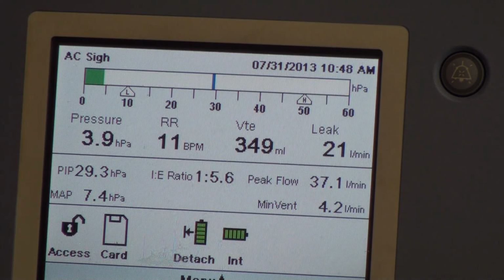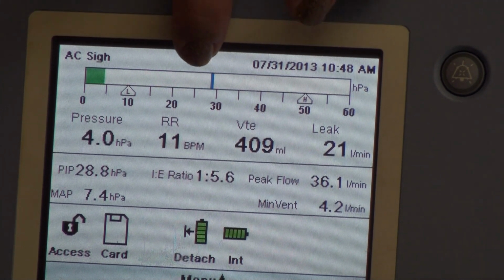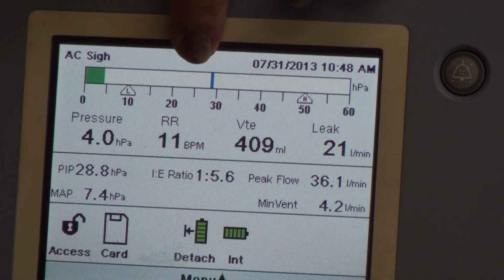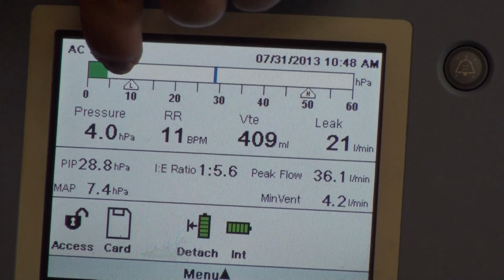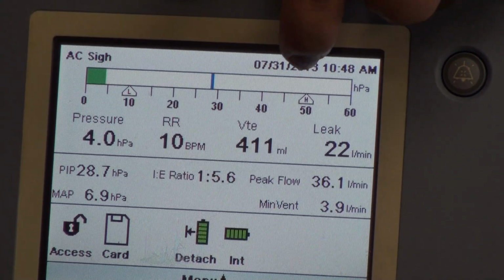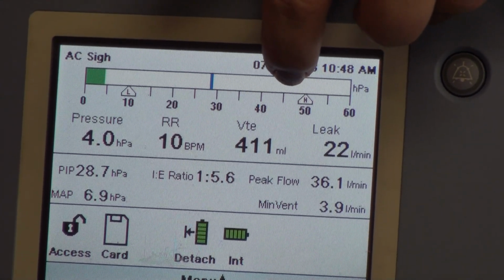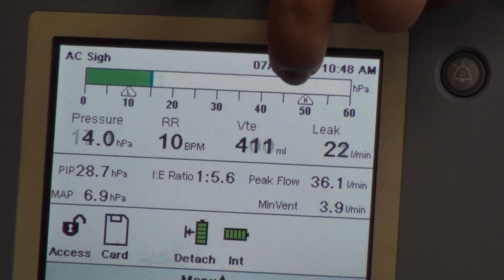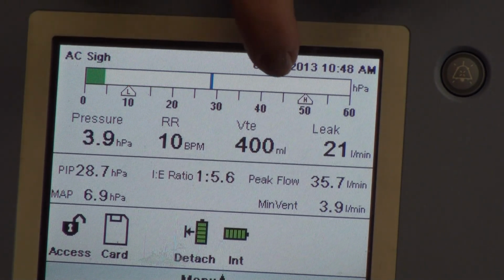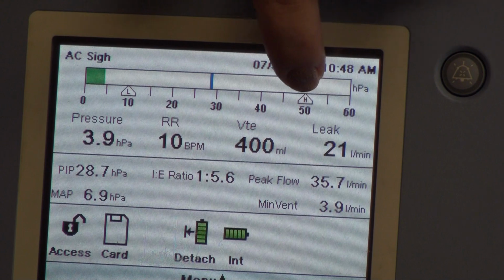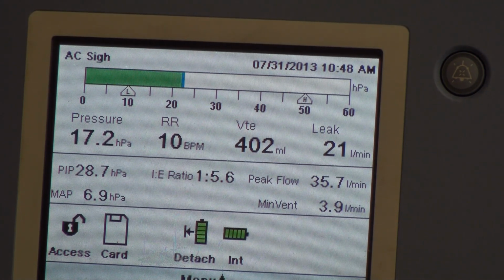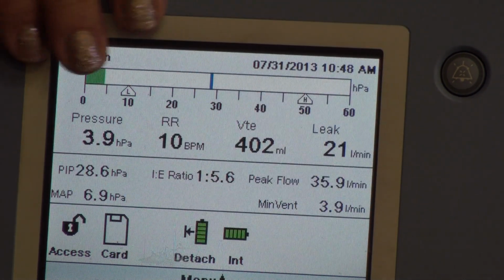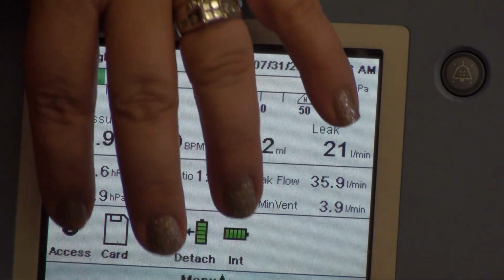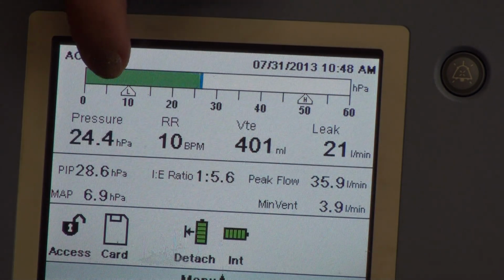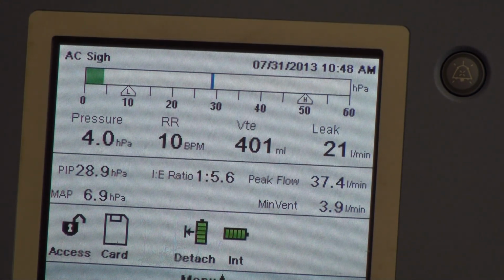Your F is going to be that peak pressure line right here. And then you have your G, your low pressure alarm, which this one happens to be set on 10, and your H is your high pressure alarm, which happens to be set on 50 on this one. These are the only 2 parameters that you will see on the front of the screen that are physician driven. The rest of these are all client data, and no actual prescribed parameters are on the front, just your low pressure and your high pressure alarms.